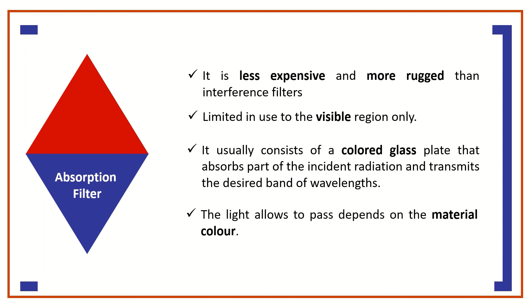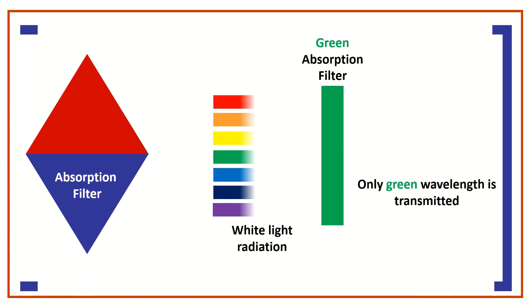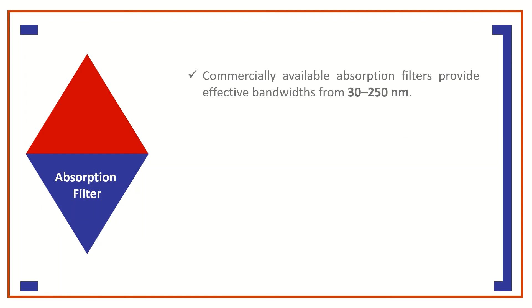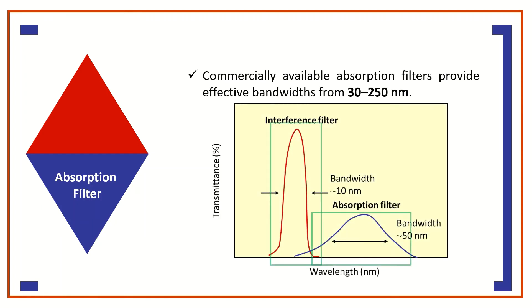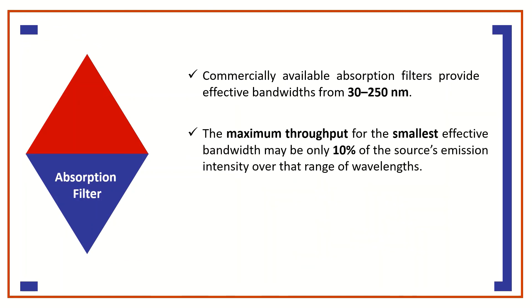The light allowed to pass depends on the material's color. For example, a green filter allows radiation in the green region to pass through it. Commercially available absorption filters provide effective bandwidths from 30 to 250 nanometers, which is wider than interference filters. The maximum throughput for the smallest effective bandwidth, however, may be only 10% of the source emission intensity over that range of wavelengths.